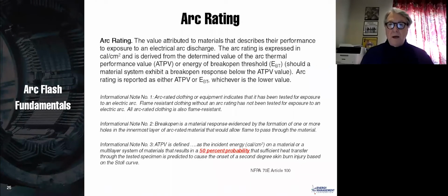Here's arc rating. Now we talk about arc rating, and really what you're talking about is the arc thermal performance value. So if you have gear, PPE, that's rated for 12 calories, then that means your arc thermal performance value is 12 calories. Here's something I think is fun. ATPV, and we're down at informational note 3, but I think you can see my cursor. ATPV is defined as the incident energy in calories per square centimeter on a material or multi-layer system of material that results in a 50% probability that sufficient heat transfer tested through the tested specimen is predicted to cause the onset of a second degree burn.